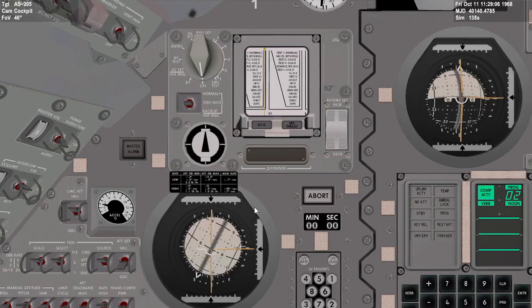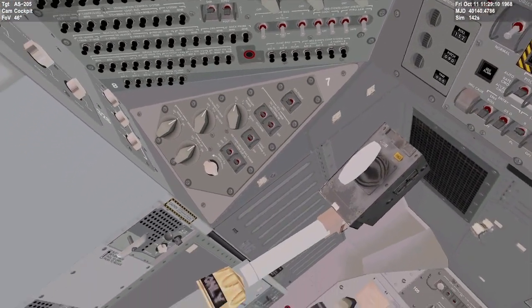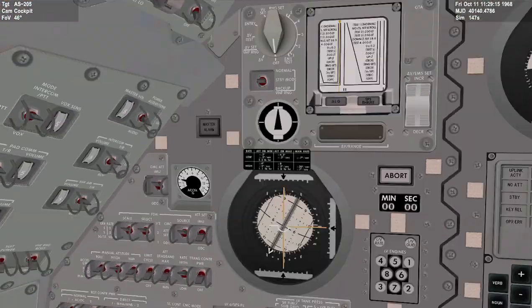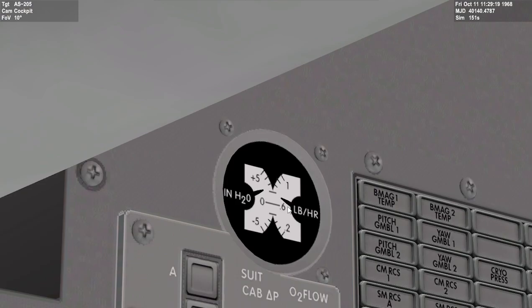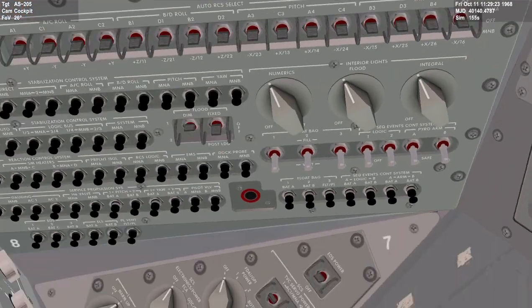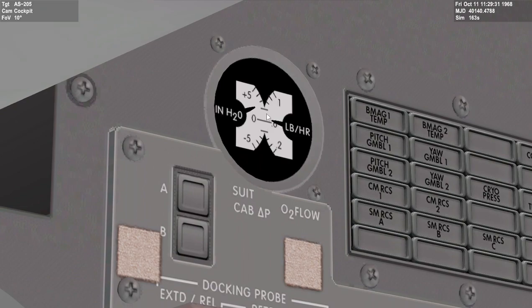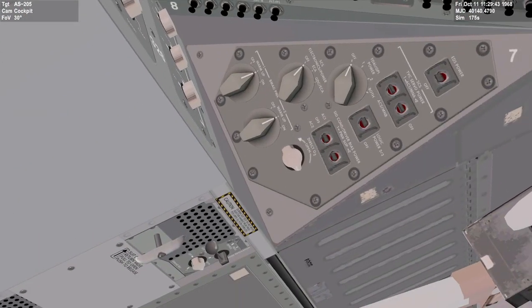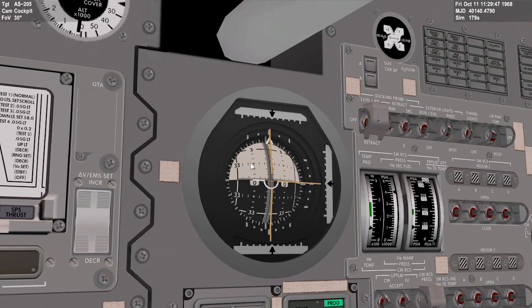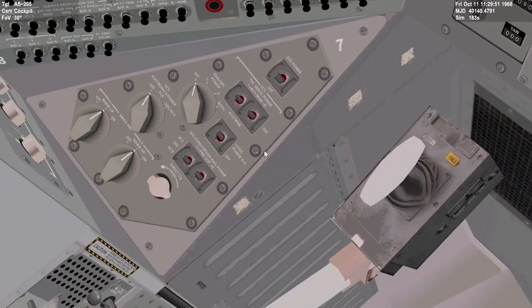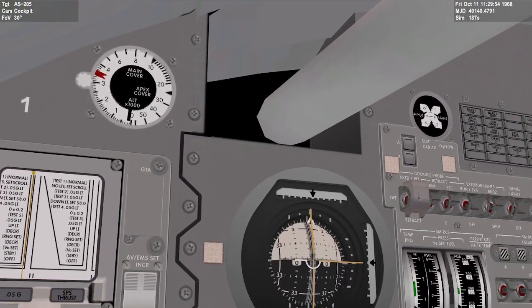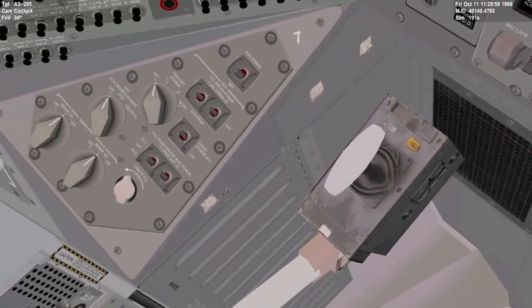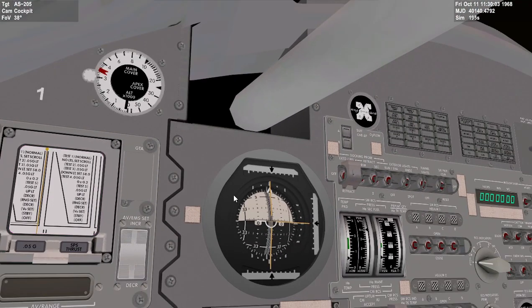Now we're going to open direct O2 to 0.4 plus or minus 0.11 pounds per hour. So that should be about right here. The checklist tells you to open it a little bit past halfway. However, I find that that's actually still a little too far. First initial setting is probably enough. Ooh, still might be too high. We might have to full close. See, now it's not enough. All right, so let's take it just past halfway, like that. It'll go full scale, and then let's take it down and see what it'll come up with then.